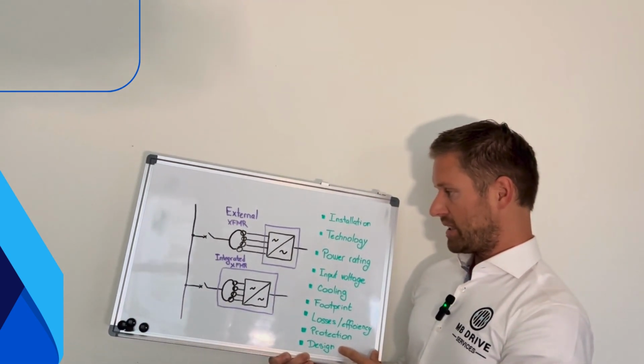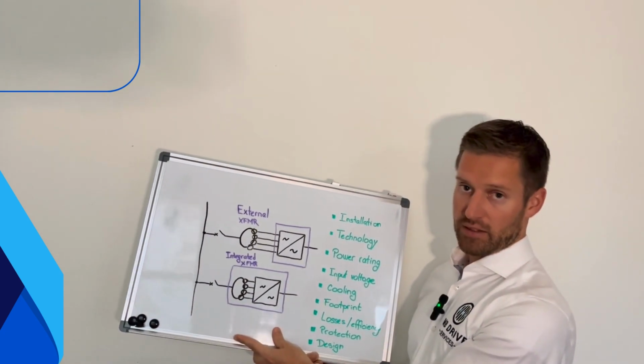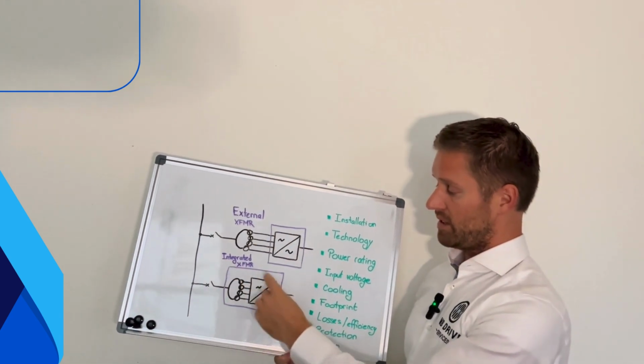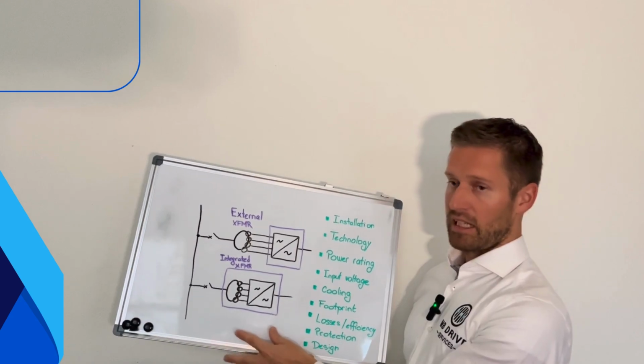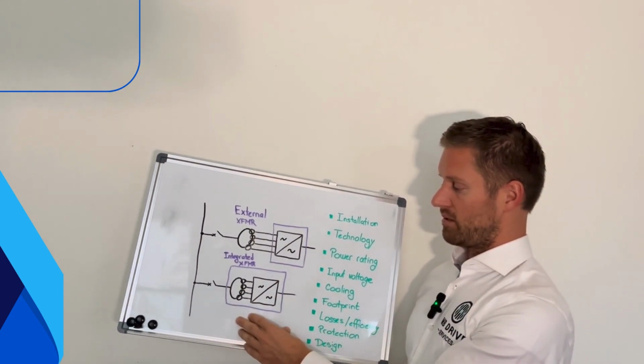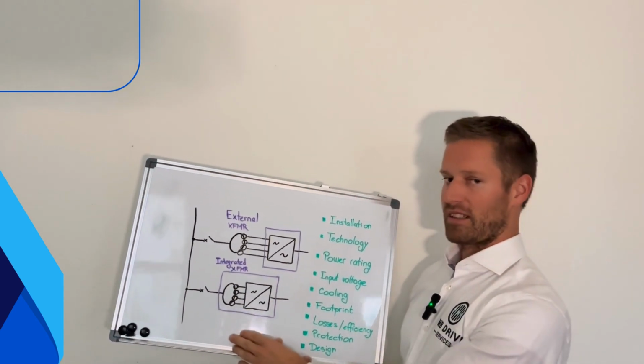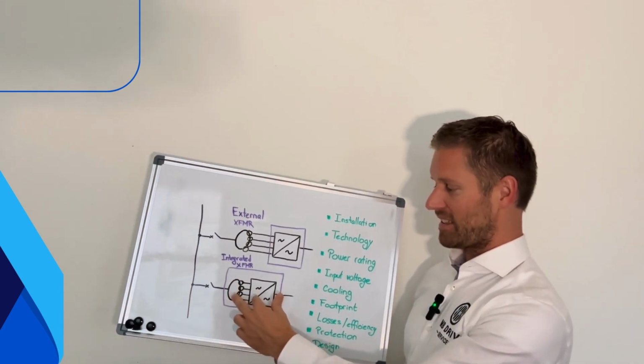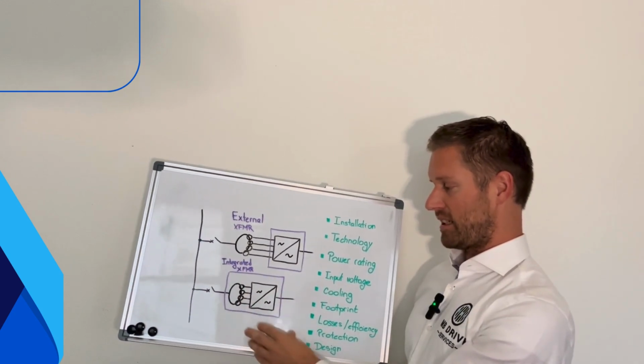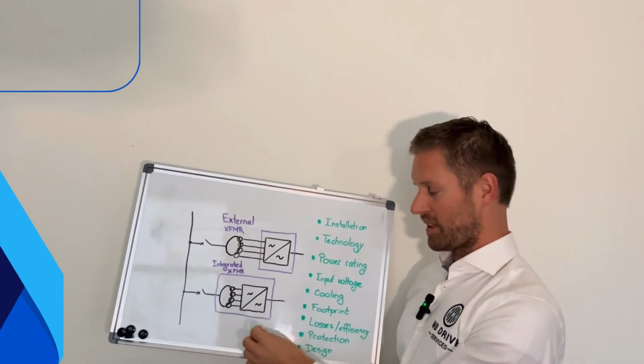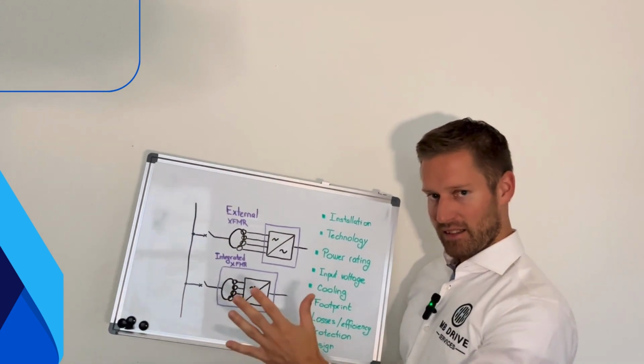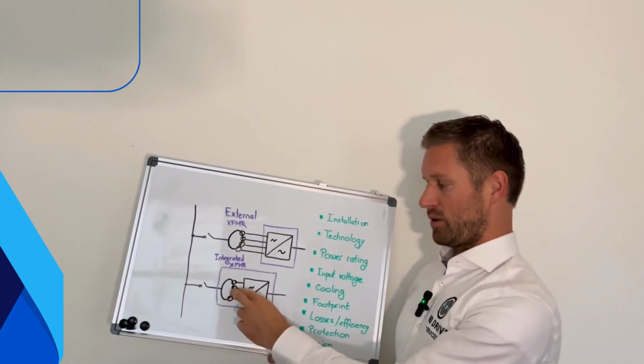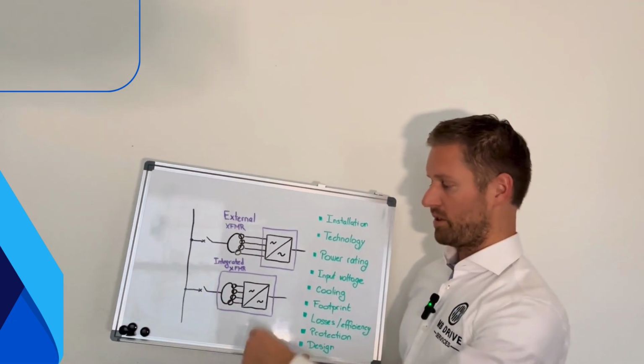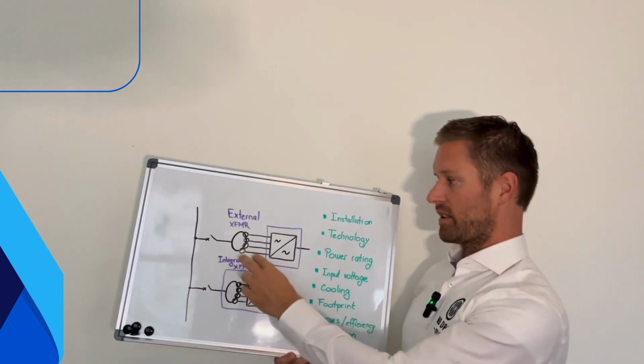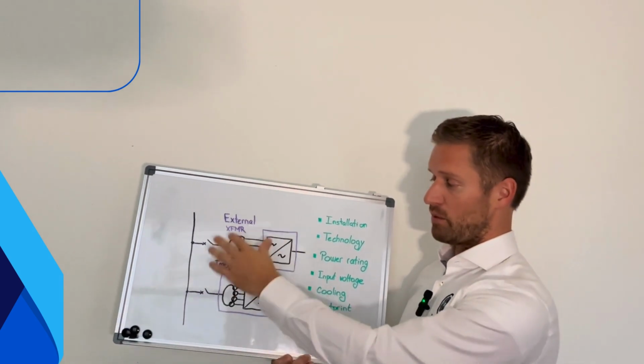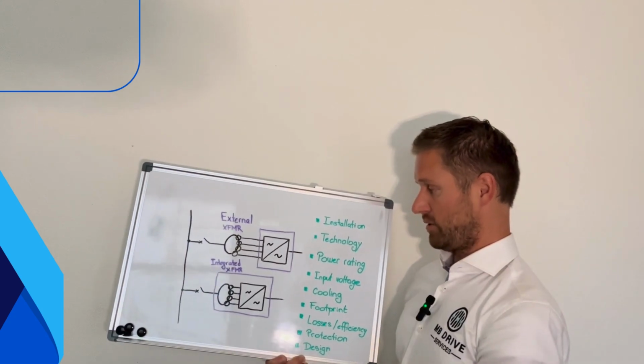Design. What I mean here is that the integrated transformer is a somewhat standardized solution. So it's part of the VFD. The VFD is standardized, and the integrated transformer is also standardized, meaning that there are maybe not so many options. If the customer comes with a detailed specification on the transformer, this is normally not the idea. With the integrated transformer, there is the manufacturer's standard design, maybe with a few options. So there is some flexibility, but you cannot completely redesign it because the dimensions of the transformer are given and so on. If you would like to reduce losses, for example, it would probably result in a larger transformer. It would not fit into the cabinet and so on. With the external transformer, especially in the large power range, this can be fully customized. So there you have more flexibility on the design.